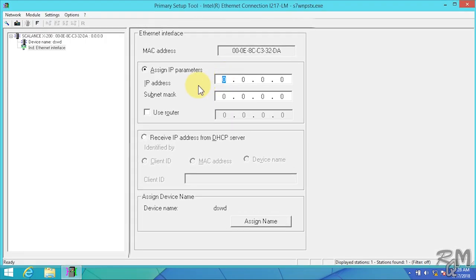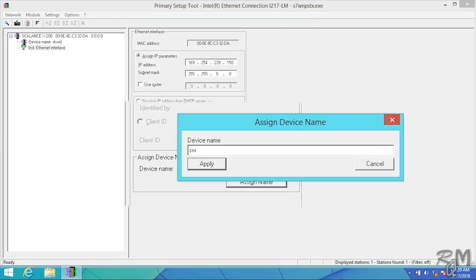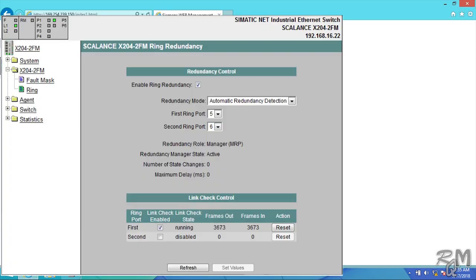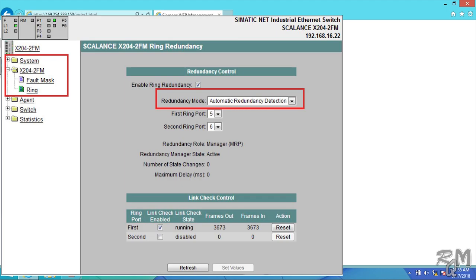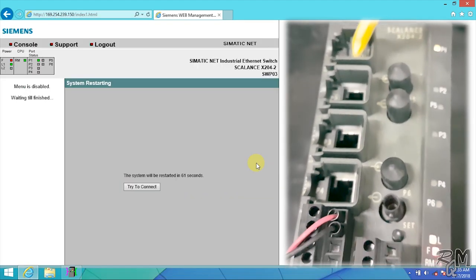After this, change three important parameters: change IP address by using Primary Setup Tool, change name of device as required by using Primary Setup Tool, redundancy mode - for example is this SCALANCE MRP manager, MRP client, or something else. After any change don't forget to click on set values button, otherwise change will not transfer to SCALANCE switch.